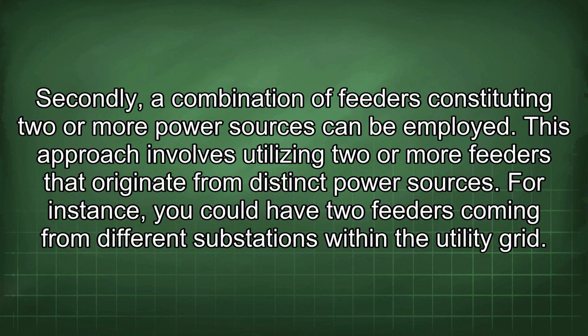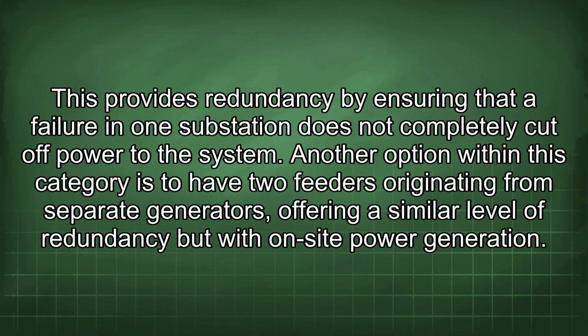Secondly, a combination of feeders constituting two or more power sources can be employed. This approach involves utilizing two or more feeders that originate from distinct power sources. For instance, you could have two feeders coming from different substations within the utility grid. This provides redundancy by ensuring that a failure in one substation does not completely cut off power to the system. Another option within this category is to have two feeders originating from separate generators, offering a similar level of redundancy but with on-site power generation.